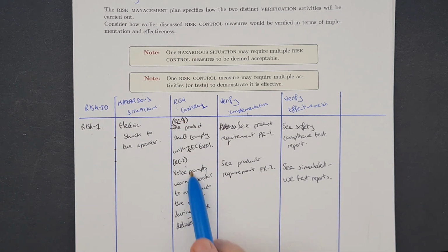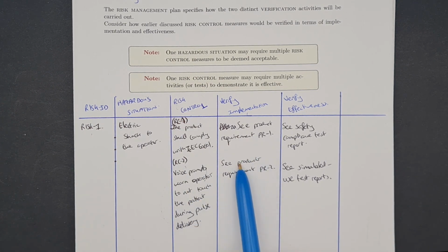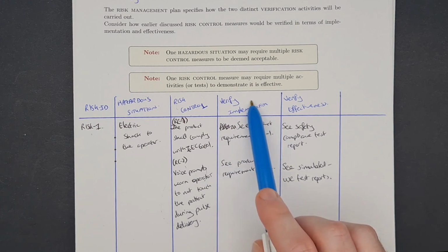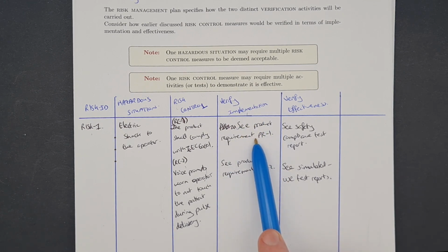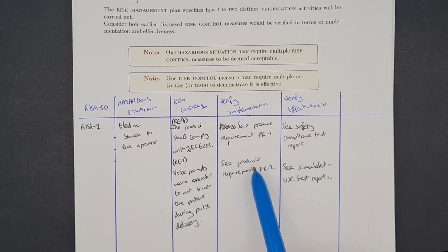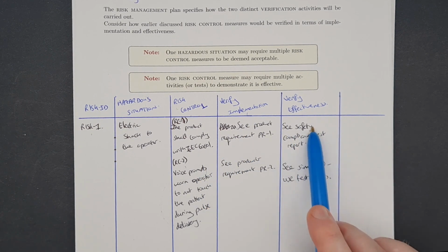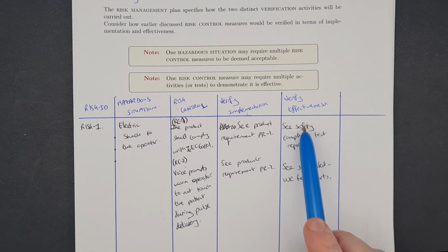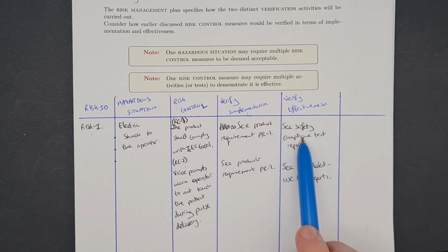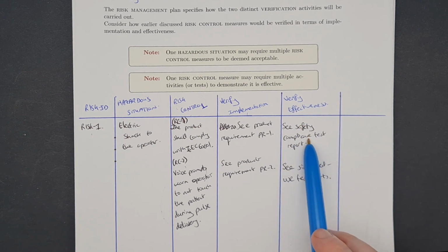We introduce risk control measures in our design, and you introduce them as requirements. You could have put here links to design details or different design outputs that demonstrate where they were implemented, but people's focus is always going to go on the testing: do you have hard evidence risk controls are effective by your testing. And of course, for different risk controls, it won't always be test reports for some standard or things like usability testing.